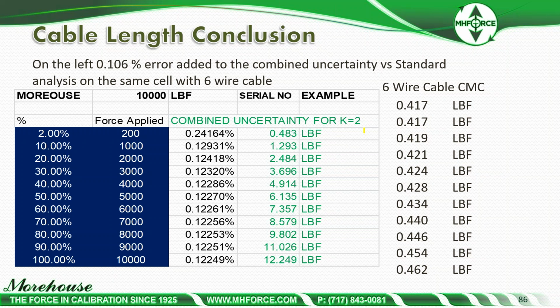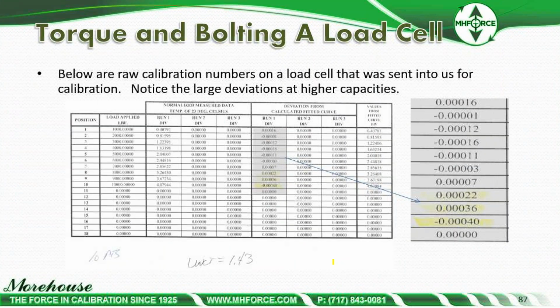What does that do? So if you're switching systems, if we do the cal and we say, hey, this is good to go at under a 1/2 pound, then you go out and switch cabling. You take that 6-foot cable to a 10-foot cable. That error becomes, what you think is a 1/2 pound becomes 12.249 pounds. So really, really significant, and really easy to change.